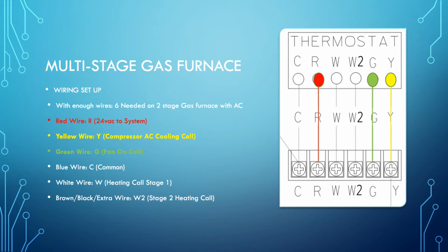with air conditioners, the thermostat sometimes does control the actual fan call, because the compressor call on the Y terminal doesn't always have to go directly to the air handler. It can bypass it technically and go straight to the air conditioner. However, it's always best to tie all the equipment together and have a leg going from the thermostat to the furnace Y terminal on the control board, and then having it branch from there to the AC, so everything is getting the same communication.